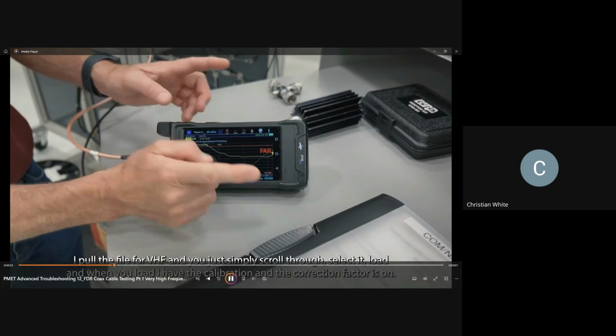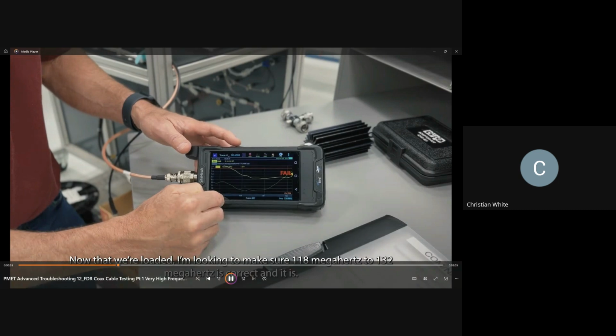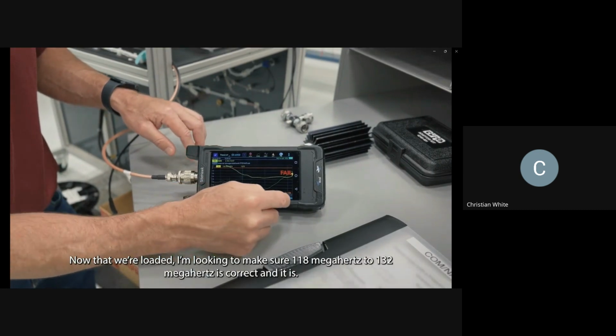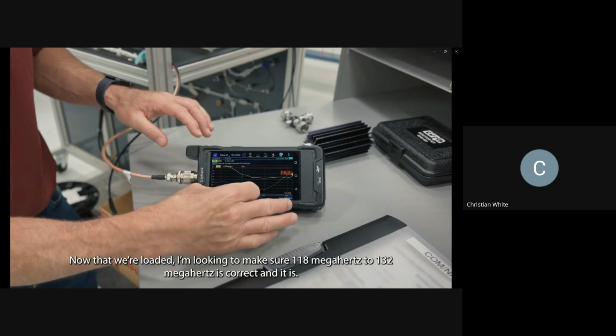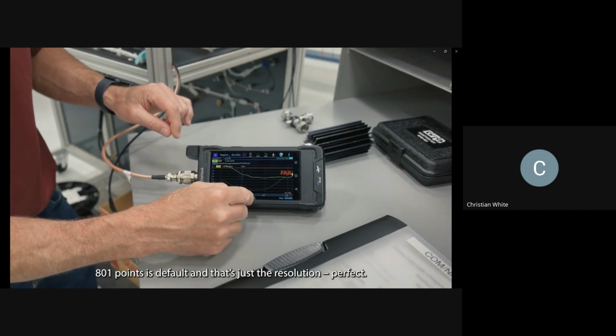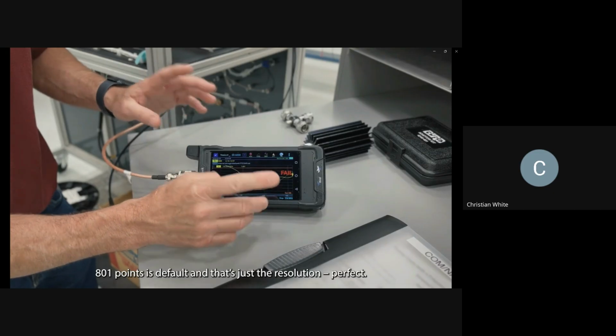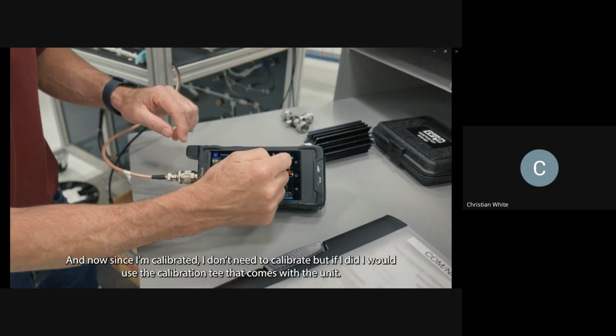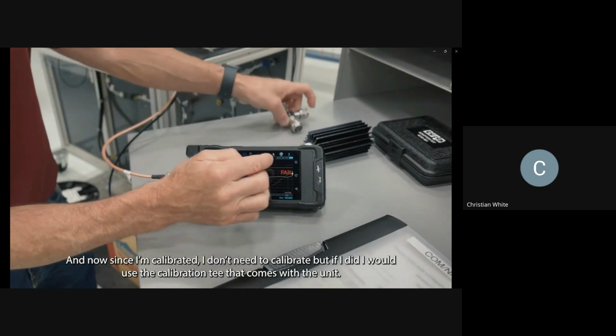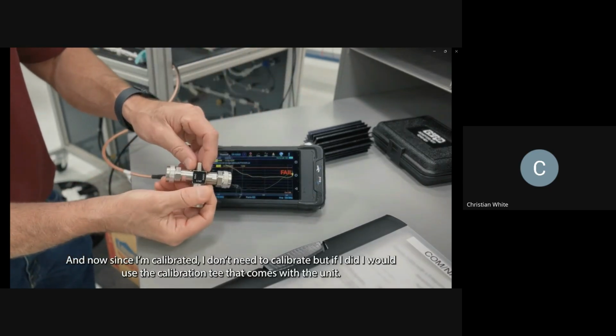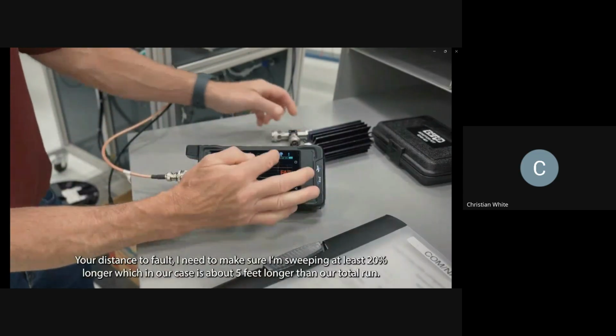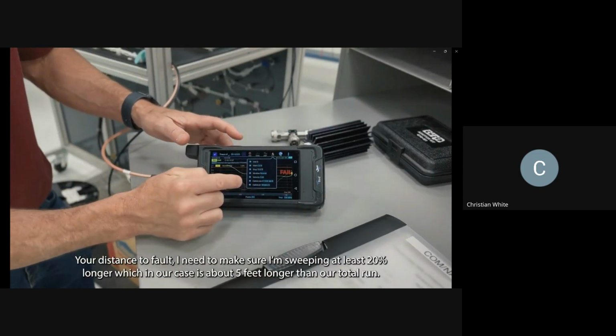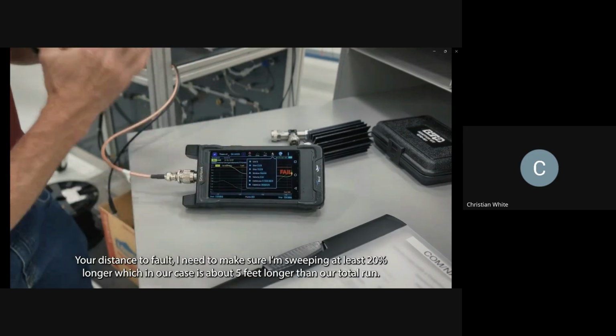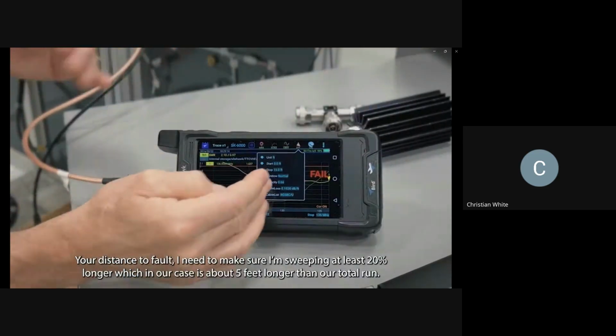Correction factor is on. So now that we're loaded, I'm looking to make sure 118 megahertz to 132 megahertz is correct. It is. 801 points is the default, and that's just the resolution. Perfect. And now, since I'm calibrated, I do not need to calibrate, but if I did, I would use the calibration T that comes with the unit. Your distance to fault, I need to ensure that I'm sweeping at least 20% longer, which in our case is about 5 feet longer than our total run.